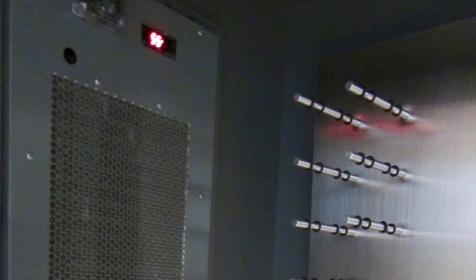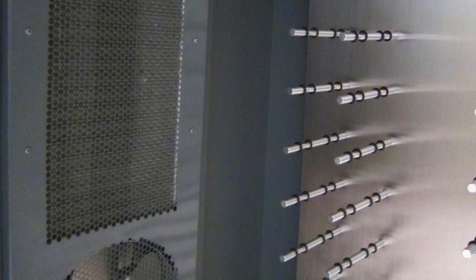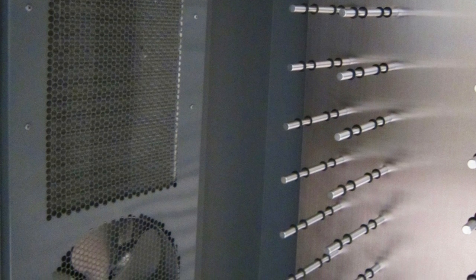We chose a cooling system which fit between the studs on the left wall. We built the wall out slightly to allow 3 inches of foam behind the cooling unit. The compressor sits outdoors in the courtyard directly opposite the cellar. We originally planned to run the lines across the ceiling to the exterior. However, once the wall was opened on the left of the cellar, we were not able to see across. This was going to be impossible because of the way the beams ran. The customer did not want us cutting into or patching his ceiling.